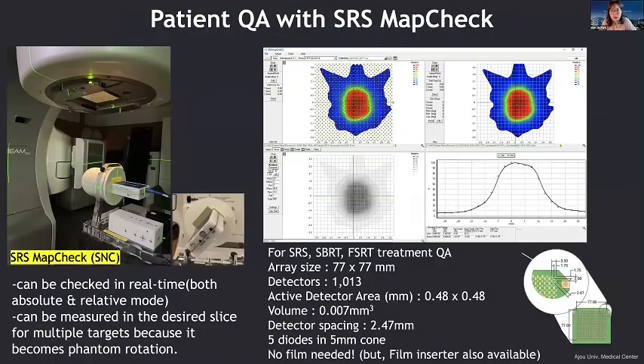And this is the result of measuring with the SRS MapCHECK that we are actively applying now. This device is actually dedicated for SRS and SBRT, so it has very high resolution with its array detectors. Don't forget it. This one is not just like the MapCHECK system. This is called the SRS MapCHECK system. Some people really confuse the SRS MapCHECK and the MapCHECK system. So this machine is highly dedicated for SRS and SBRT treatments.